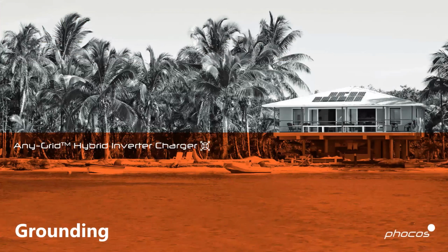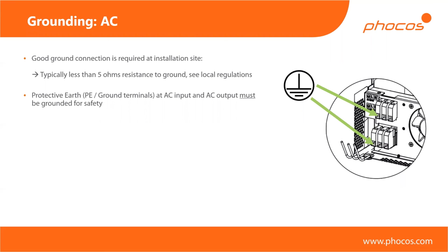Now the final subject is grounding, and at the very end we have some recommendations as well. For grounding, grounding is obviously very important for safety. I don't have the time to explain why, but those that are installing the system should know. The mandatory grounding on the AnyGrid is both on the AC input and the AC output. Obviously, if you're just using one of the two, then you just need one ground point. They're connected internally. So you must absolutely connect those for safety.